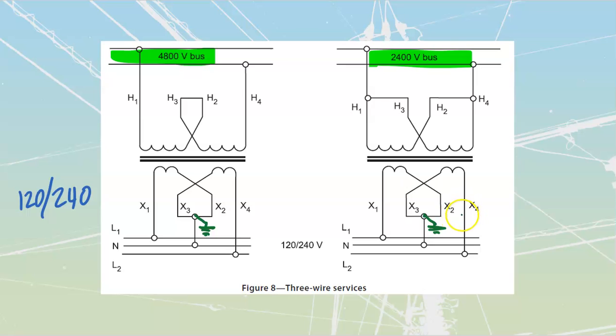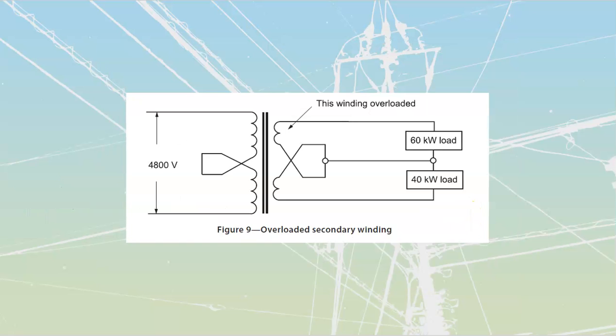Okay. I will be able to deliver the full 100 kVA out of these transformers. However, what I do need to do is make sure that I balance that. I don't know if you have done a lot of panel connections, but when you do your final power up of the system, one of the last checks that you should always be doing is sticking an ammeter around each of your two lines. We're going to go around line 1, we'll stick another ammeter around line 2, and we double check and make sure that the current is balanced.